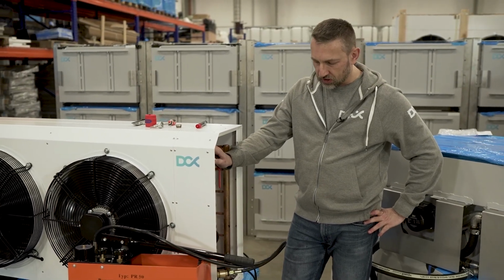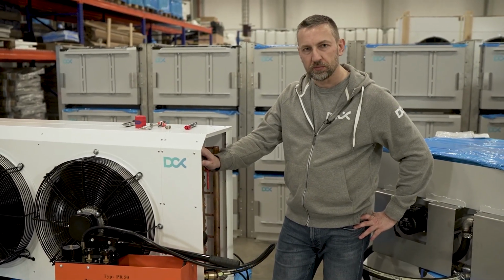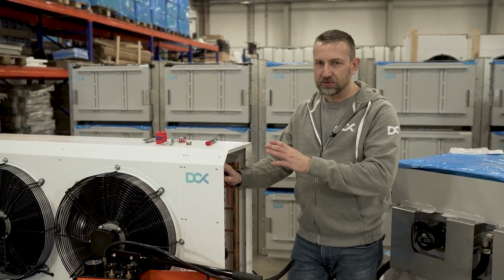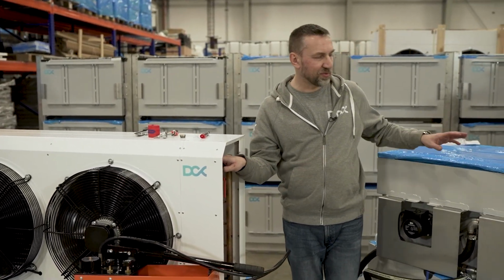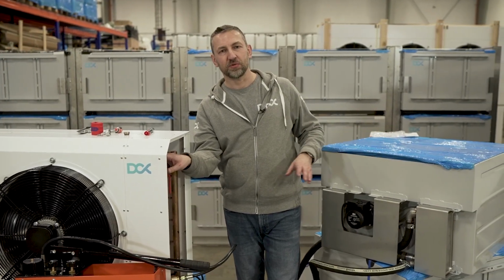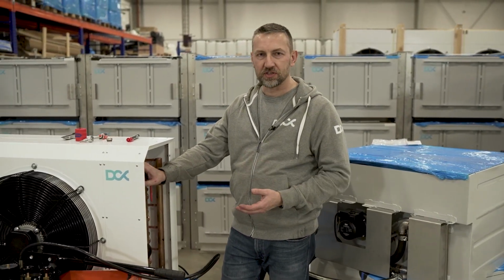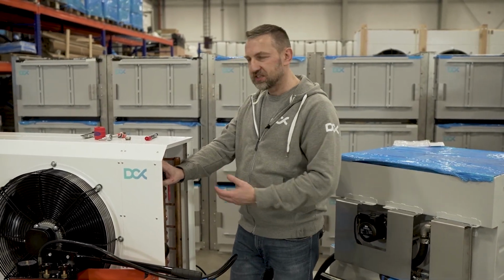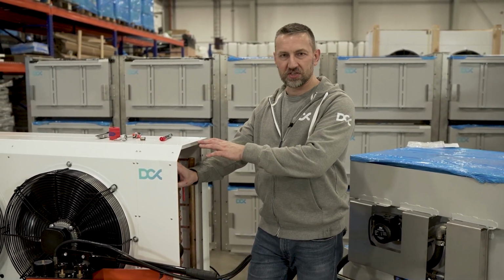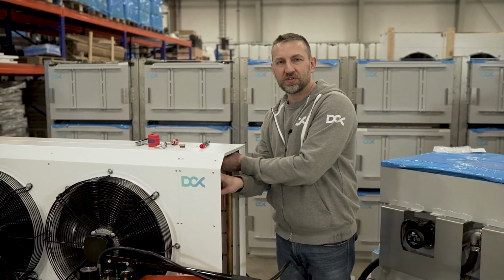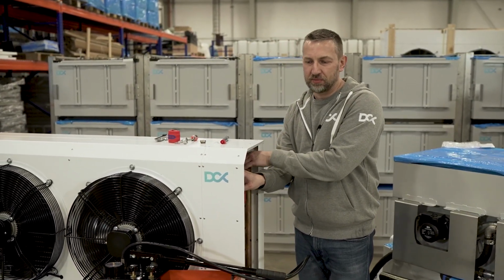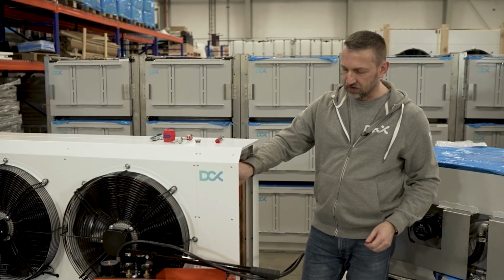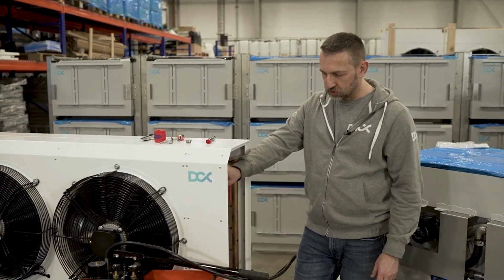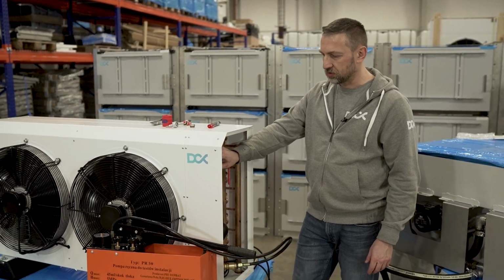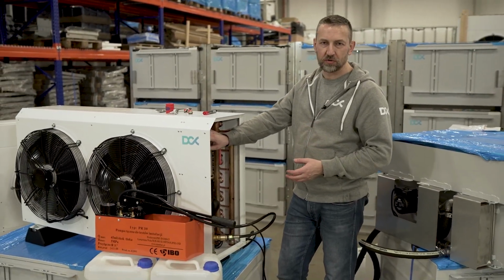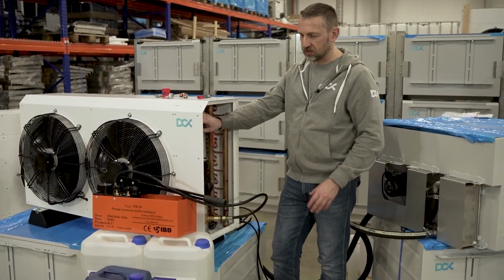Just one more add-on in terms of the connection of the pump and filling the system. Now the system is pretty cold. When you start the operation, when you put the load inside, you will get an additional amount of heat, and that will release additional air from all the pockets here. So you will have to check those air vents again and maybe release some additional air from the system. Simple as that. And you should get that set up pretty quickly. It usually takes an hour or so just to properly fill the system, connect it, and all.